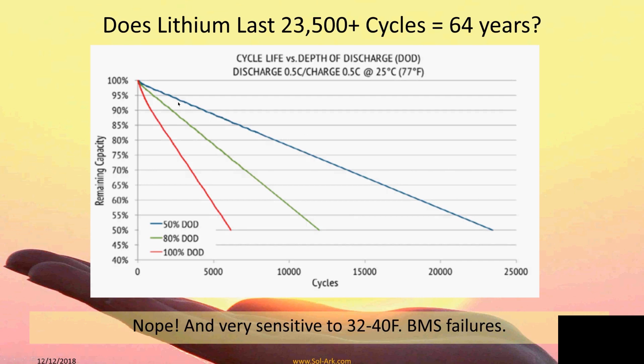What is reality is that you'll get about 80% capacity, and after about 85% it'll just drop off like a rock. We ended up spending over $200,000 in battery research and testing — we tested LFP, NMC lithium, wet cell batteries, regular AGMs, and a new technology called carbon AGMs. Lithium has a lot of hype because of charts claiming you can discharge 100% every day and it won't matter — but that's not true either.